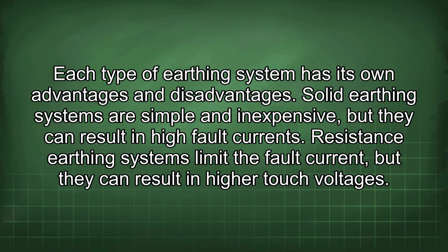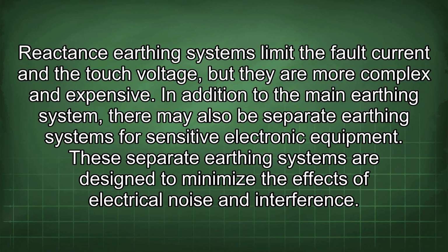Solid earthing systems are simple and inexpensive, but they can result in high fault currents. Resistance earthing systems limit the fault current, but they can result in higher touch voltages. Reactance earthing systems limit the fault current and the touch voltage, but they are more complex and expensive. In addition to the main earthing system, there may also be separate earthing systems for sensitive electronic equipment. These separate earthing systems are designed to minimize the effects of electrical noise and interference.